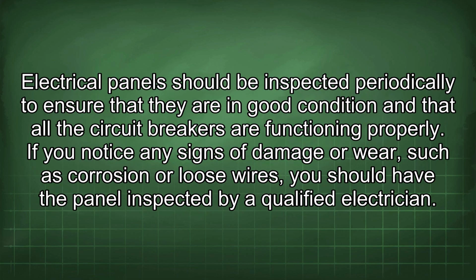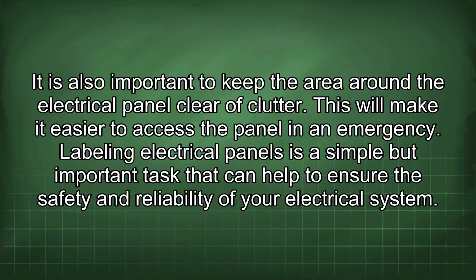Electrical panels should be inspected periodically to ensure that they are in good condition and that all the circuit breakers are functioning properly. If you notice any signs of damage or wear, such as corrosion or loose wires, you should have the panel inspected by a qualified electrician. It is also important to keep the area around the electrical panel clear of clutter. This will make it easier to access the panel in an emergency.